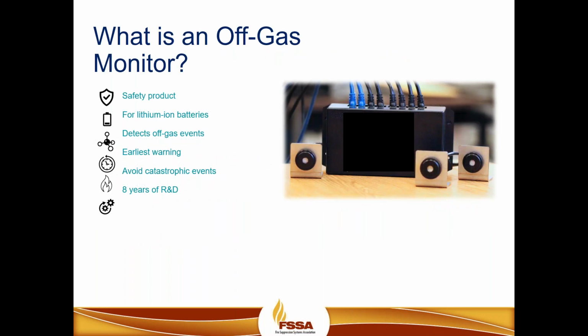If you haven't seen what an off-gas monitor looks like, this is a good illustration. You have a controller here at the top connected to some sensors that are placed out in the field, typically in the rack, in the path of airflow, actively looking for those VOCs or off-gas levels. And that's being communicated to the BMS and/or the fire alarm control unit, possibly even being used for suppression release or extinguish release as well.